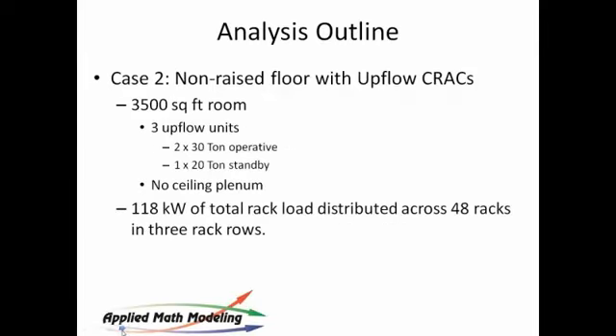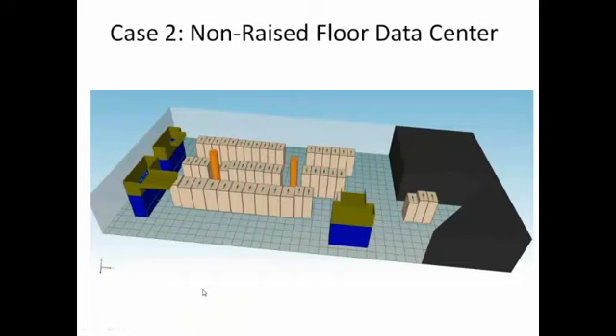So let's look at another one. Here is another case, very quickly. This is a non-raised floor design with upflows. This is one I was exposed to not too long ago, and it's an adaptation of one that I had seen. So here's the original design. This is a screenshot coming out of CoolSim 4. You see here, this is a non-raised floor data center, and they've got 3 units in here: 2 30-ton units over here, and a 20-ton unit here. They've put these scoops at the top and are just blowing the air straight into the top of the room, and the thought is that it will come across and fall down because of the weight of the air. It's cold, so it's going to drop and fill that room.